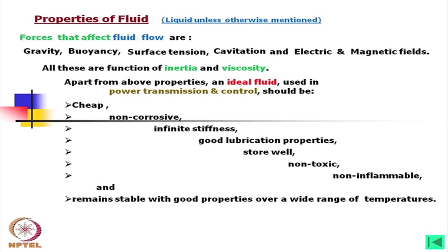Most importantly, the fluid should also be non-inflammable, because in many applications there is a possibility it may catch fire. For example, in mining applications we have to take extra precaution so that the oil does not catch fire. It should remain stable with good properties over a wide range of temperatures.